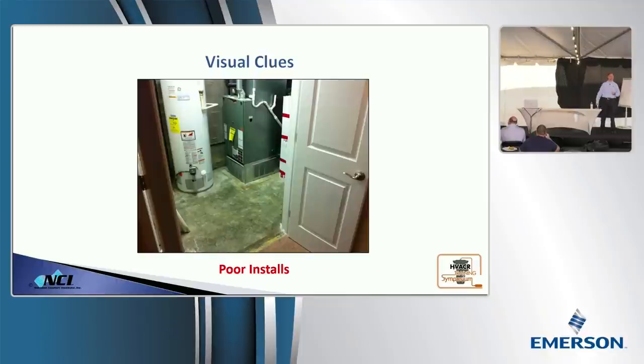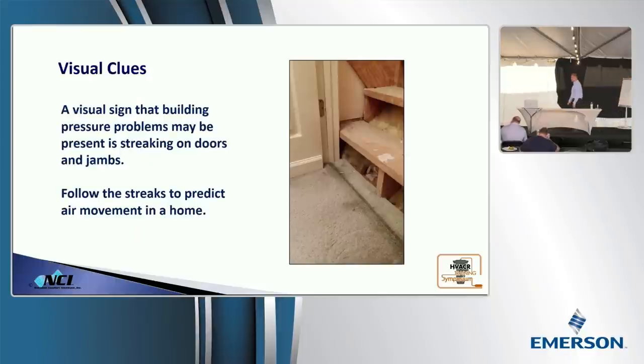Somebody said a lot. The return air is all being pulled out of a plenum underneath the furnace. And we've got a solid condition space manual damper on there. We shut the damper, what happens? Oh, air takes the path of least resistance, 1 CFM in, 1 CFM out. We just created a chain reaction there. Oops. So these are the things that we can find as we start to just look at things. Then we start to measure them.